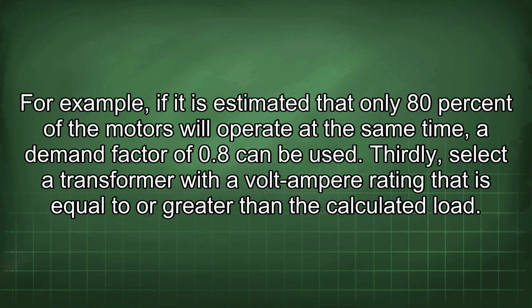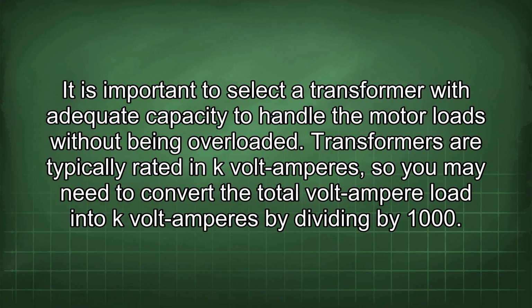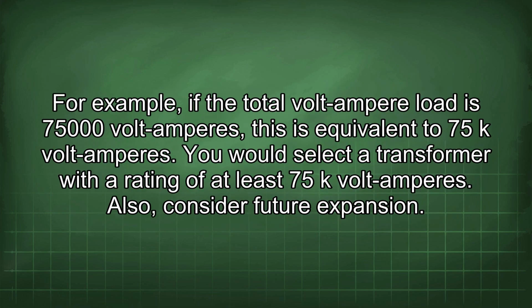Thirdly, select a transformer with a volt-ampere rating that is equal to or greater than the calculated load. It is important to select a transformer with adequate capacity to handle the motor loads without being overloaded. Transformers are typically rated in kilovolt-amperes, so you may need to convert the total volt-ampere load into kilovolt-amperes by dividing by 1000. For example, if the total volt-ampere load is 75,000 volt-amperes, this is equivalent to 75 kilovolt-amperes. You would select a transformer with a rating of at least 75 kilovolt-amperes.